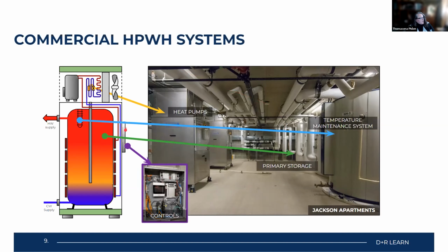Now, it's also important to note that most, but not all, heat pump water heaters on a residential scale do have controls that are capable of communicating with an app on your phone or your tablet. And they also will typically have a CTA 2045 communication port, and it will be grid connected, so it can also respond to demand response events. The same goes for the commercial controls. These are typically off-the-shelf modules for the controls, or components for the controls, and not only are they interconnected with the building management system through a BACnet or LonWorks, but they are also connected to the grid through that EcoPort that I spoke of earlier. So if we want to take a look here, we're going to walk through this building at the very end of the presentation.